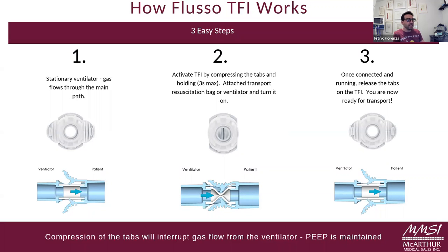Let's break this down into three easy steps. Step one: Flusso TFI is in the system and gas is going straight through, business as usual, with no change to anything you're doing in the ICU. Now say you want to change an HME or switch to a resuscitation bag. You activate the tabs by compressing them, which compresses the tubing inside the device, temporarily occluding the center. Once you reconnect it to the resuscitation bag, transport vent, or stationary vent, you just let go and everything goes back to normal. It's a very easy in-service for your team: squeeze it when you want to use it, let it go when you don't.